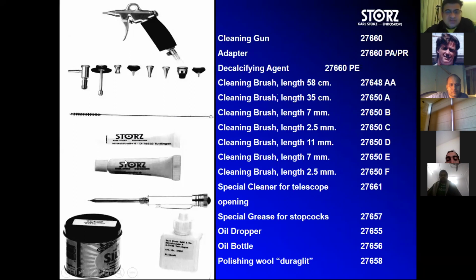Now this is a special lubricant for the stopcocks. That means the neuroendoscopy therapeutic sheath has an inlet channel and an outlet channel. So when you open the lower lock, there are nuts there and they have threads. During corrosion over a period of time, these threads are going to wear off. So even if you close, you will find the artificial CSF, the RL, is coming out, and you're not happy. So when you lubricate, it's like lubricating a cycle chain. The threads are intact and it will have a long life expectancy.